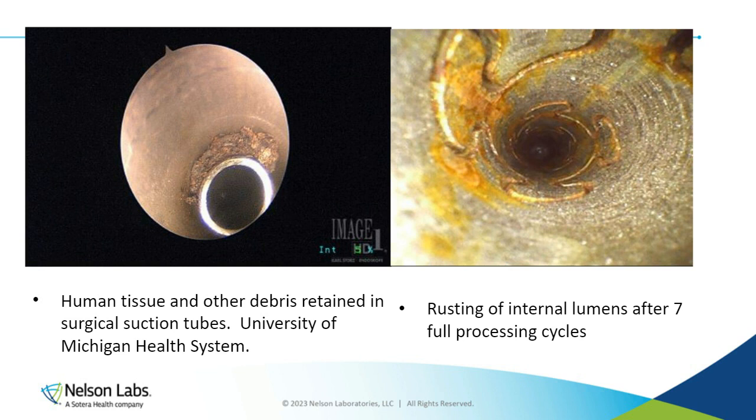So regardless of it passing all the analyte testing, which would have been fine, the device internally was destroyed. And we had to report back to the sponsor and tell them, listen, your devices have passed everything, they look great, but the internal portion is destroyed and the detergent residuals, you failed. So you would have to go back and redesign the internal portion to make sure that it can withstand the chemicals and the water that's being used to clean these devices. So something to think about, just food for thought.